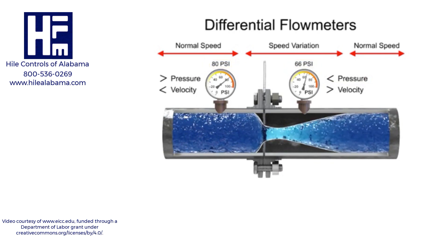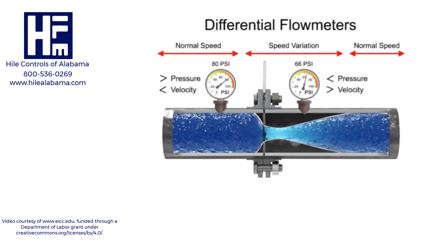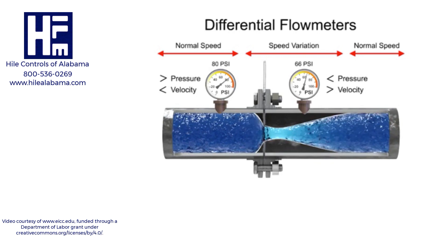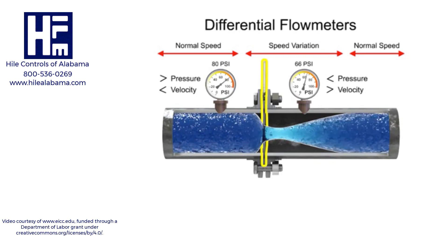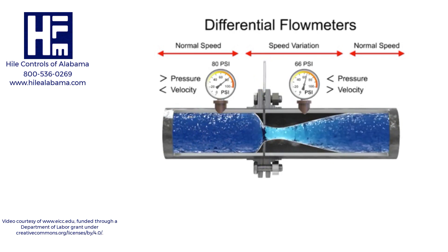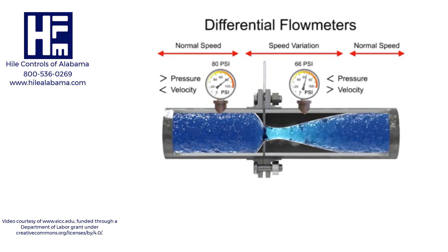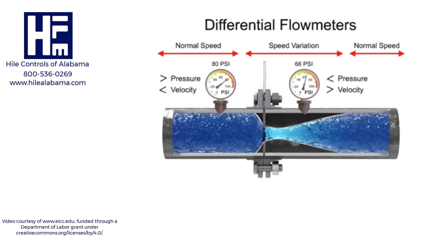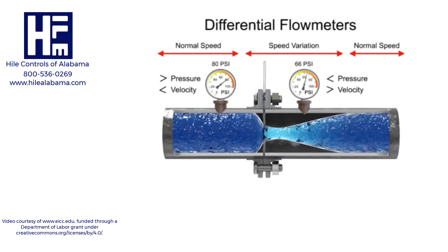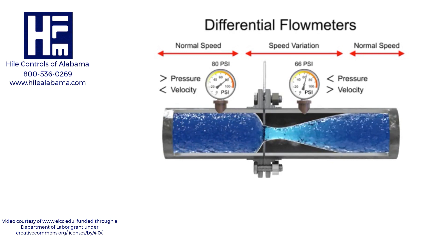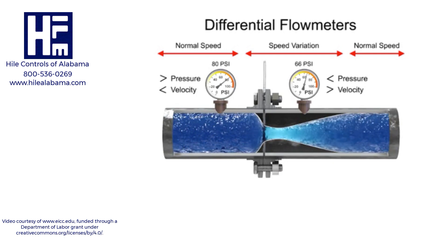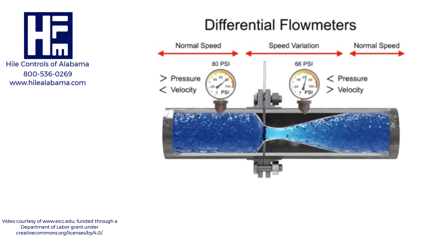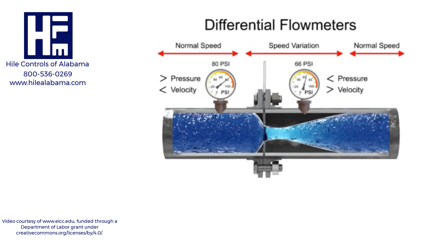As the fluid flow rate increases through the pipe, back pressure on the incoming side increases due to the restriction of flow created by the orifice plate. The pressure of the fluid at the downstream side of the orifice plate is less than the incoming side due to the accelerated flow. With a known differential pressure and velocity of the fluid, the volumetric flow rate can be determined.